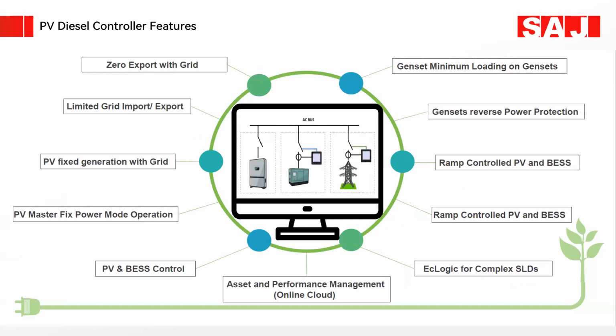The PV diesel controller features zero export with grid. If you don't have a net metering option at your premises and you have installed a solar system, then from the PV diesel controllers you can control zero export to the grid, limited grid import and export, and PV fixed generation with the grid. PV master fixed power mode operations, PV and BESS control, asset and performance management online cloud, and genset minimum loading or genset reverse power protection.